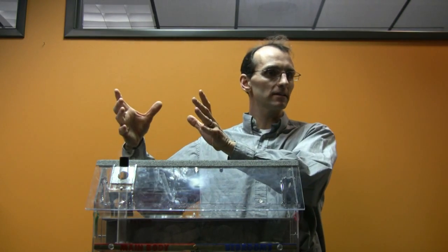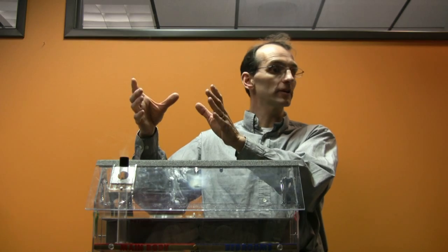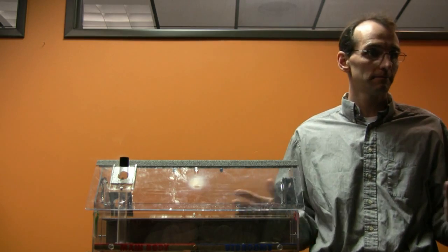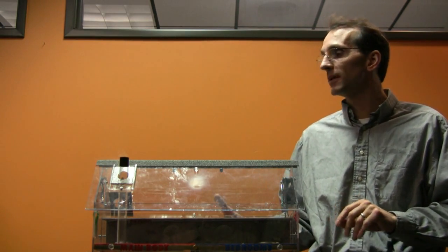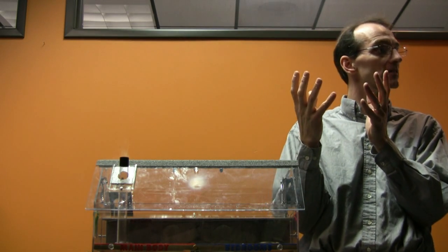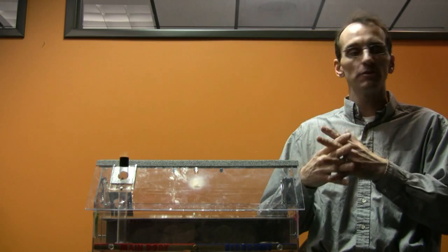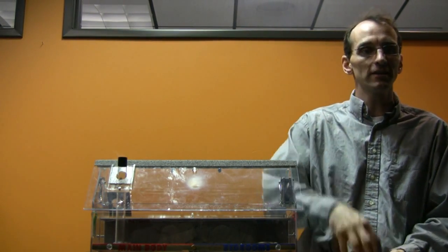But if you just left the old flue in place, and now your water heater is connected to a flue that was designed for a furnace and water heater combination, your flue for the water heater is oversized now. That water heater may have a hard time heating that flue up in a fast enough fashion. The way flues and chimneys work, they warm up, the stack effect is created within the chimney, and exhaust air is pulled out.